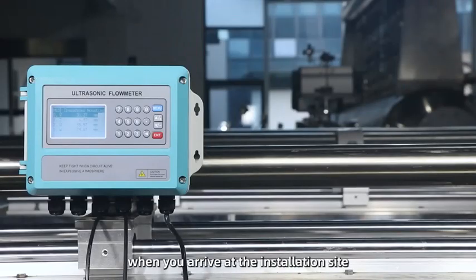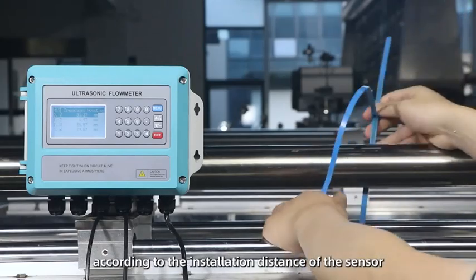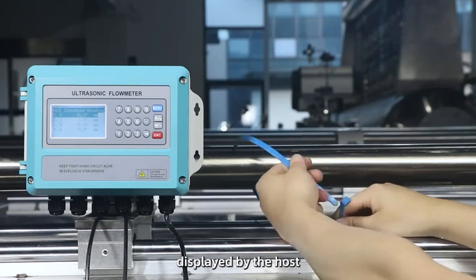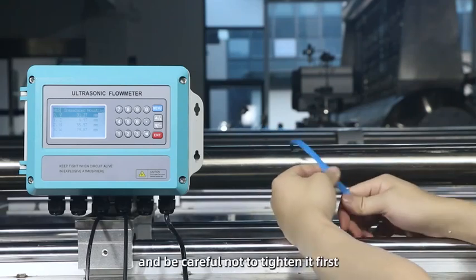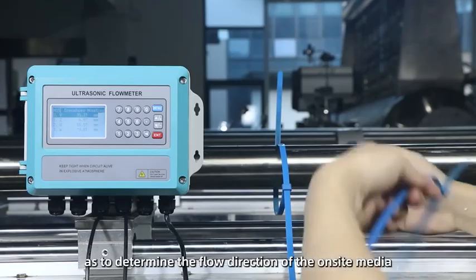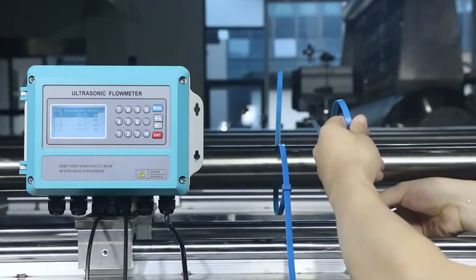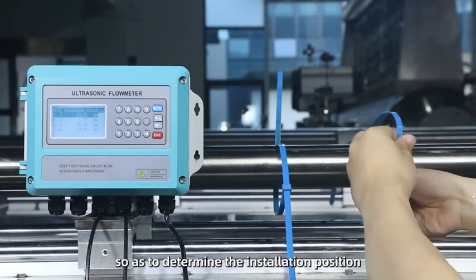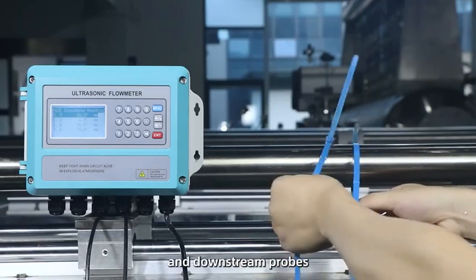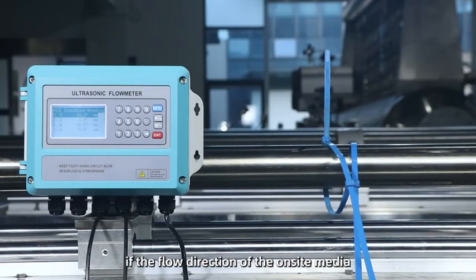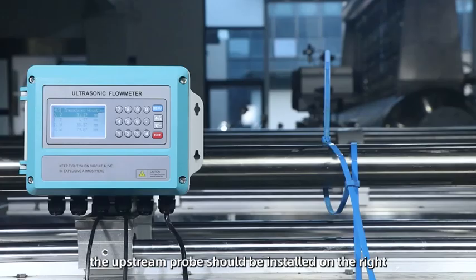When you arrive at the installation site, fix the cable tie on the pipeline according to the installation distance of the sensor displayed by the host, and be careful not to tighten it first, so as to determine the flow direction of the on-site media, so as to determine the installation position of the upstream and downstream probes. If the flow direction of the on-site media is from right to left, it can be determined that the upstream probe should be installed on the right and the downstream probe should be installed on the left.